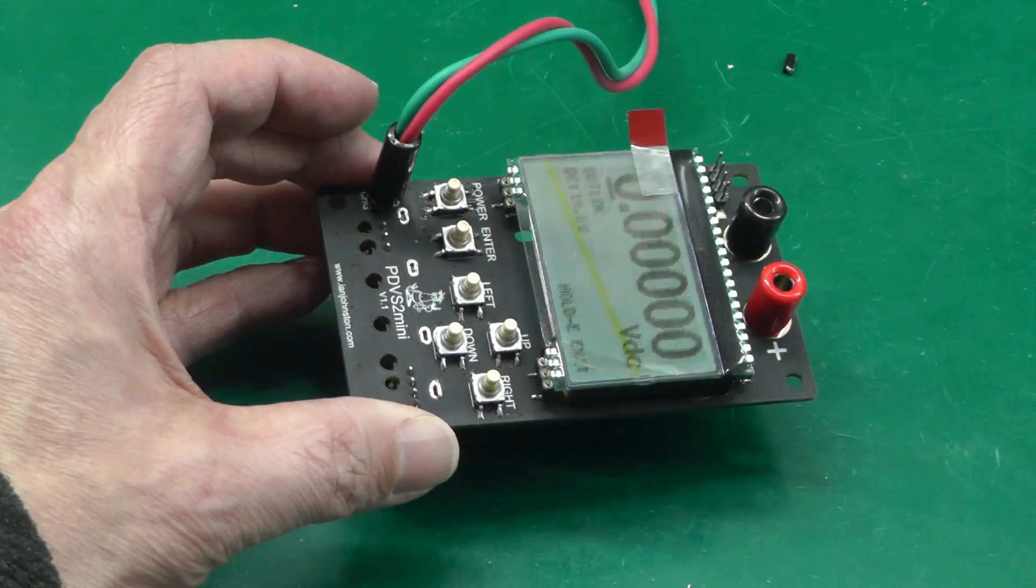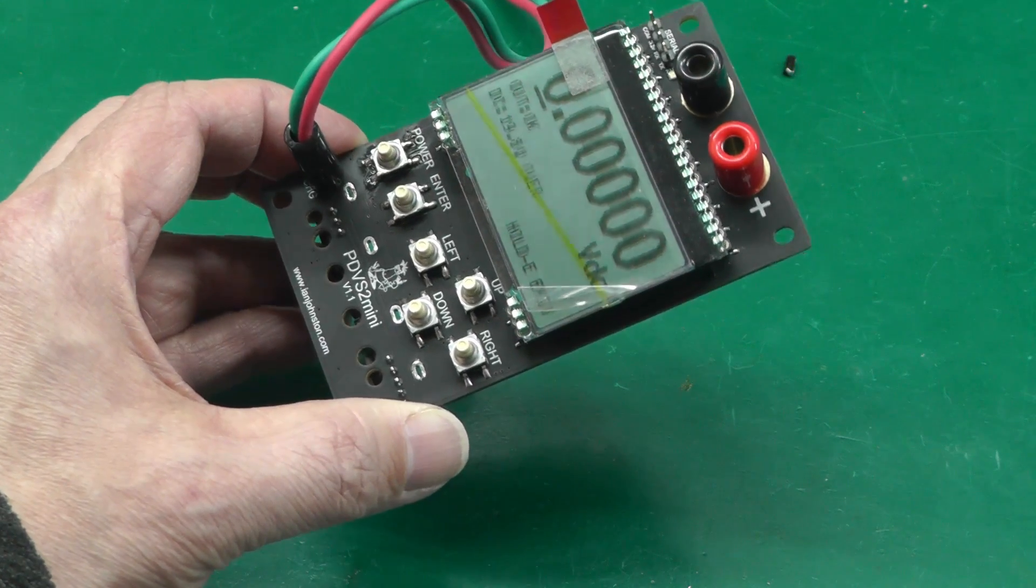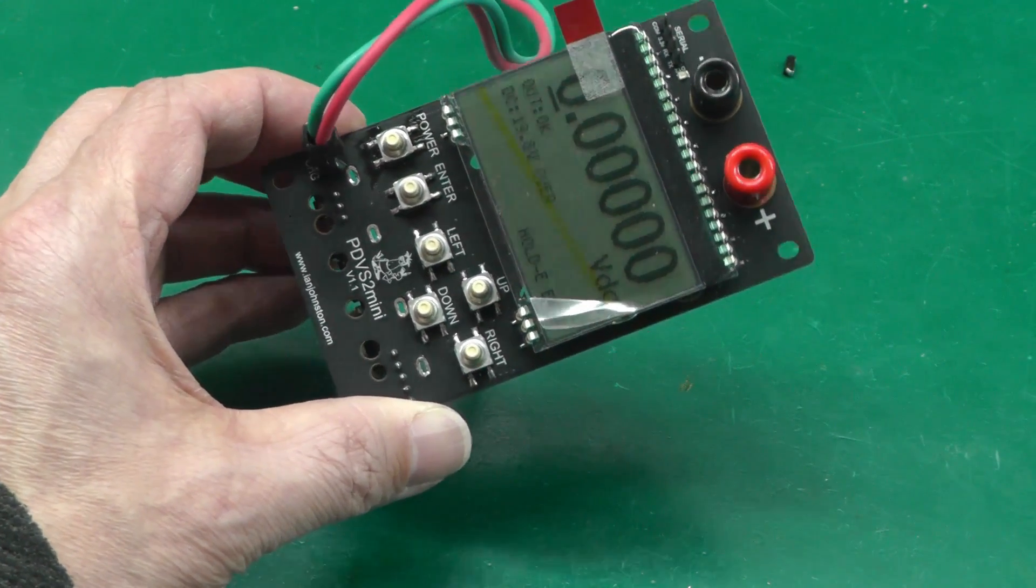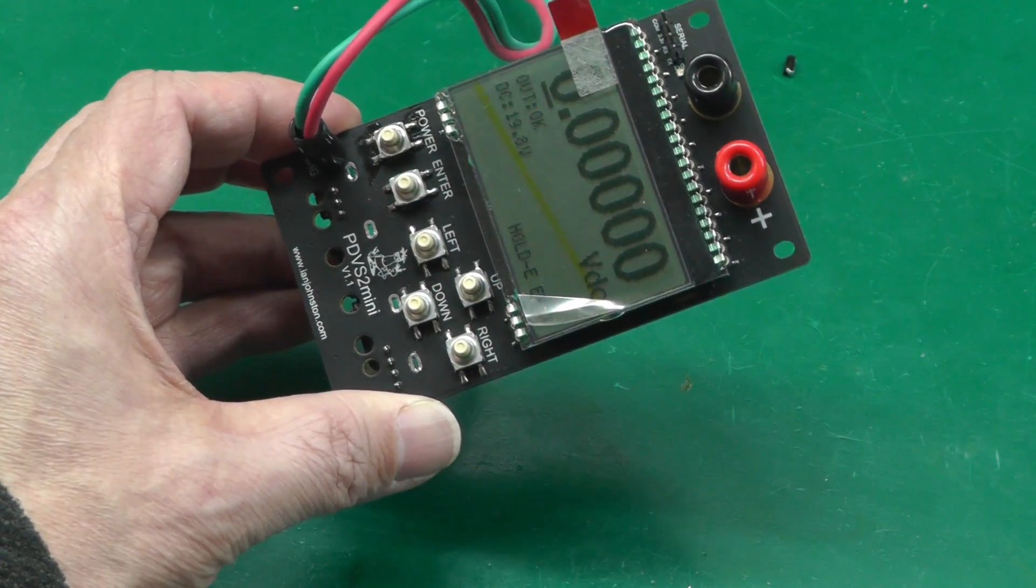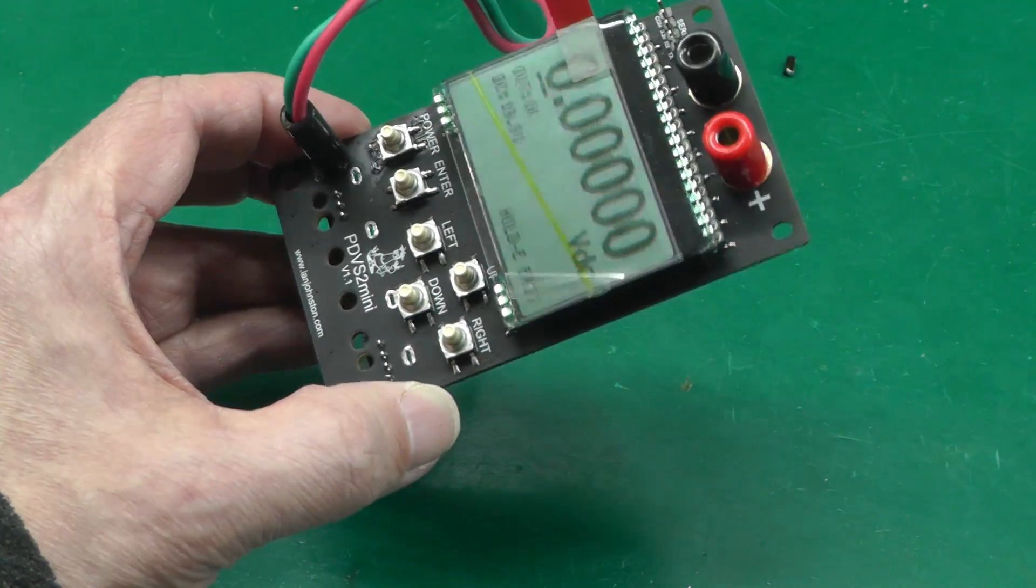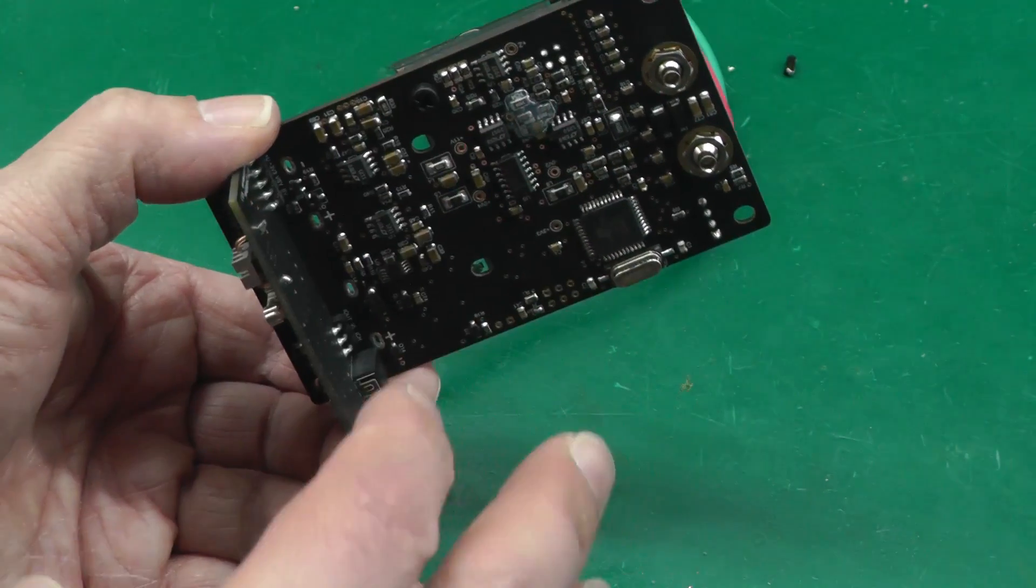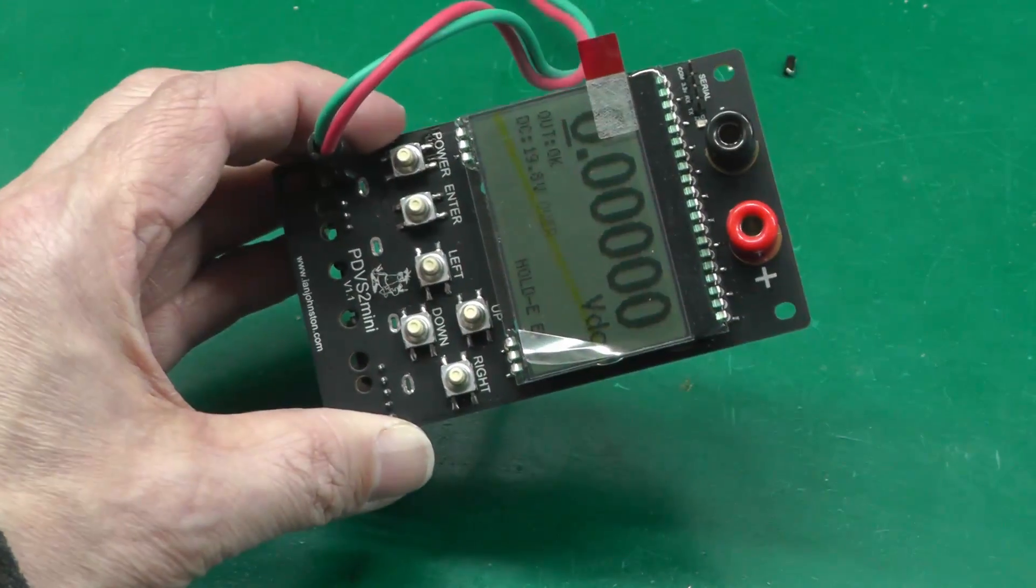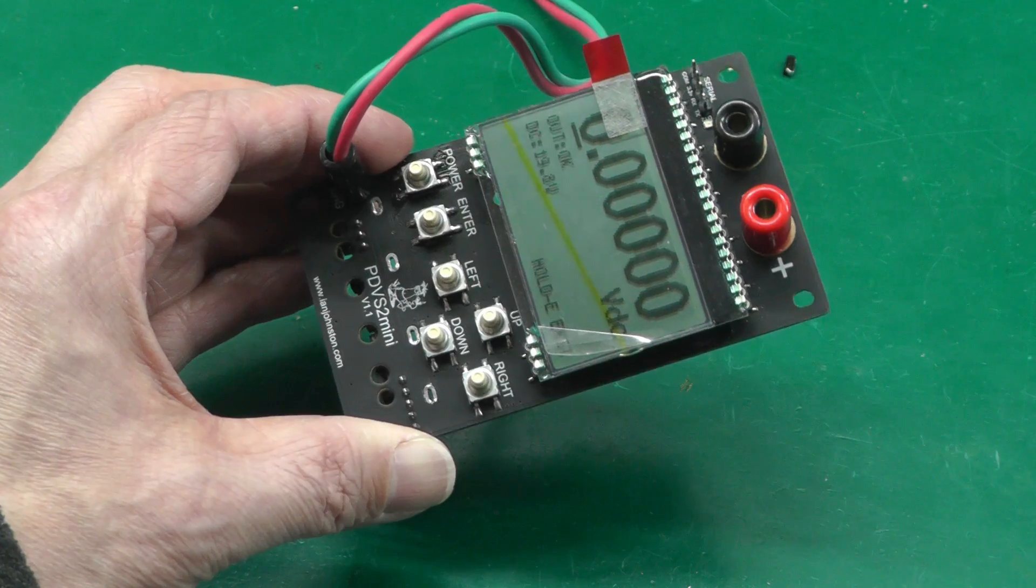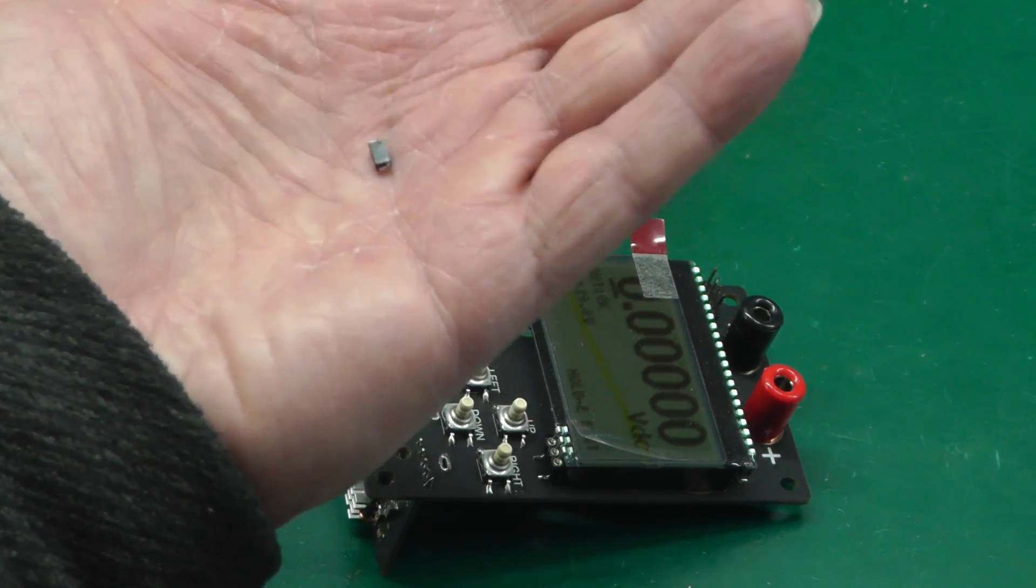Now of course when you're testing, things never go to plan and I've got a faulty one here that I've actually just repaired. This one powered up perfectly, seemed to go through all the pre-calibration okay, and it would just switch off randomly - sometimes it lasts an hour, sometimes it lasts 15 seconds. It took quite a bit of time to fix this one. I was all over the place because the processor can shut down the board, you've got a power switch, you've got a power circuit, you've got quite a lot there that can go wrong.